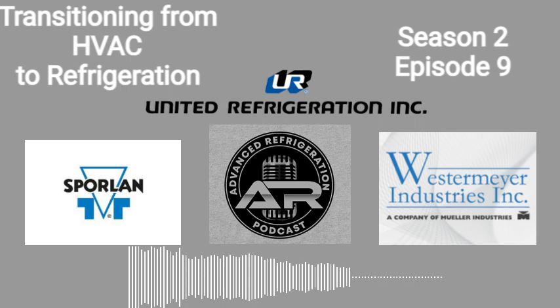What you just said is the most ridiculous thing ever. It's not going to plug up as fast. Okay, how about we just properly purge and do the job? And I go, what costs more money in the end? Me pumping down a system and pulling a screen, shutting a hand valve and pulling a screen? Yeah, it takes 30 seconds. Or me cutting a dryer out that takes 2 to 3 hours.